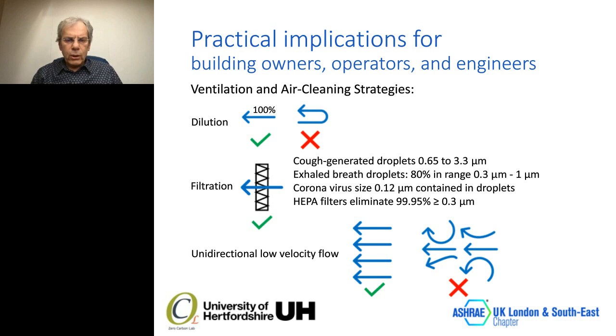Also, unidirectional low velocity flow helps to clean droplets from the room air. Low velocity unidirectional airflow works as a piston in an internal combustion engine, and takes particles out of the room. But if you have turbulent flow, as in the bottom right-hand side of this slide, then that is not going to clean the air, and you might actually increase the transmission of airborne infection.